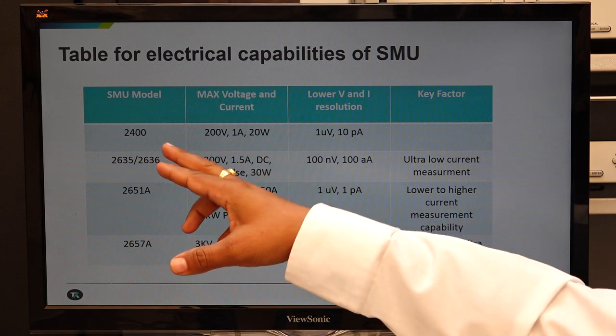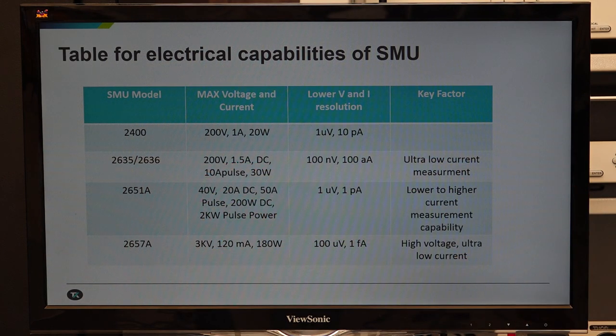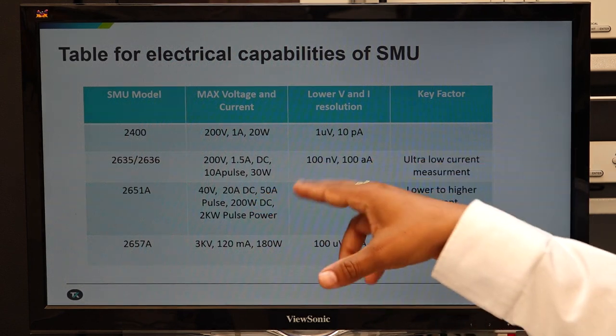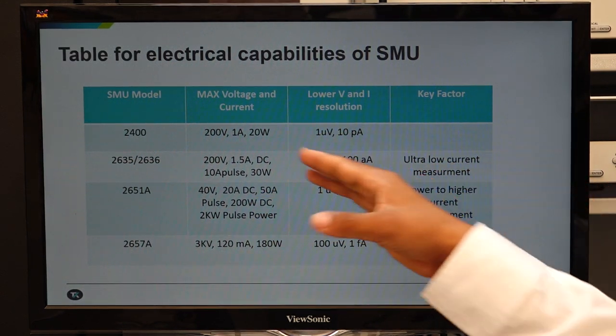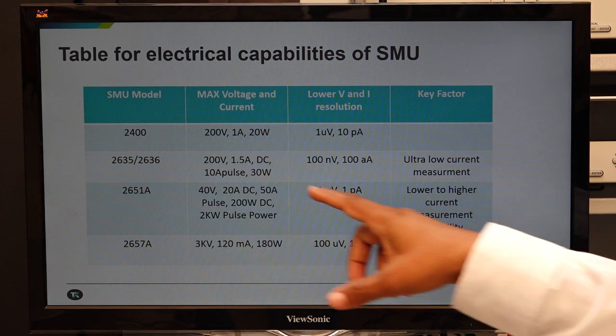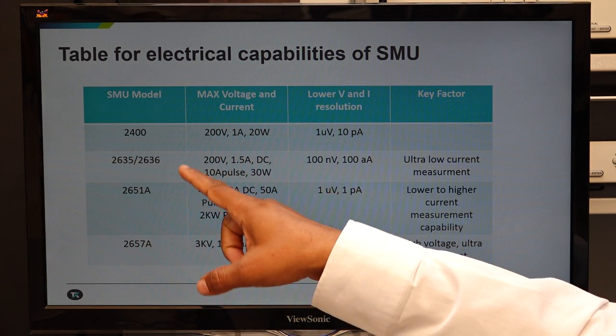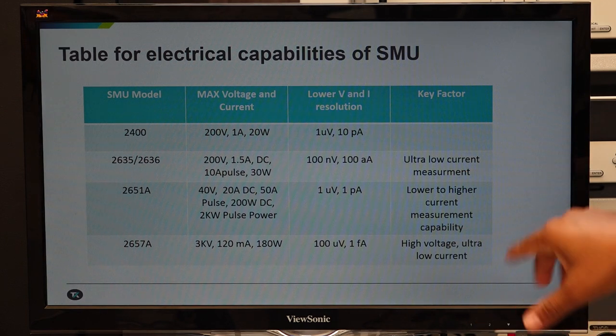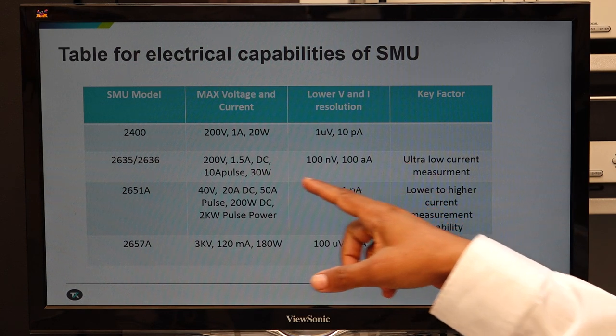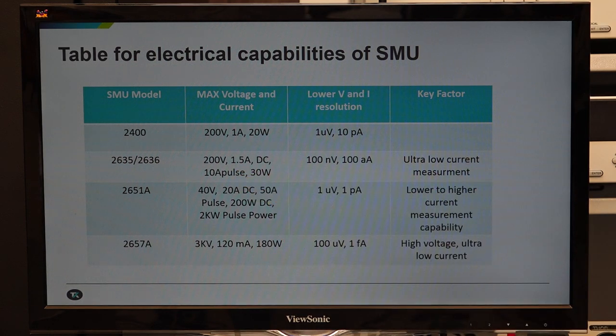We have four different types of SMU. The general purpose 2400 SMU is capable of sourcing voltage up to 200 volts, current up to 1 ampere with 20 watt power rating. On the lower side, it offers resolution of 1 microvolt for voltage and 10 picoampere for current. The 2635 single channel or 2636B dual channel SMU is an ultra-low current SMU for measuring very, very low current, capable of 200 volts and 1.5 ampere DC.